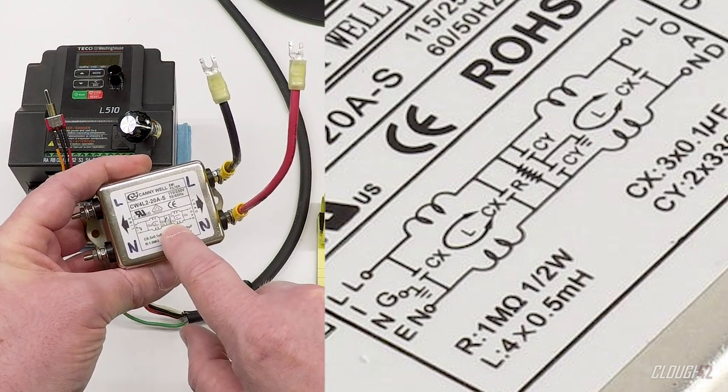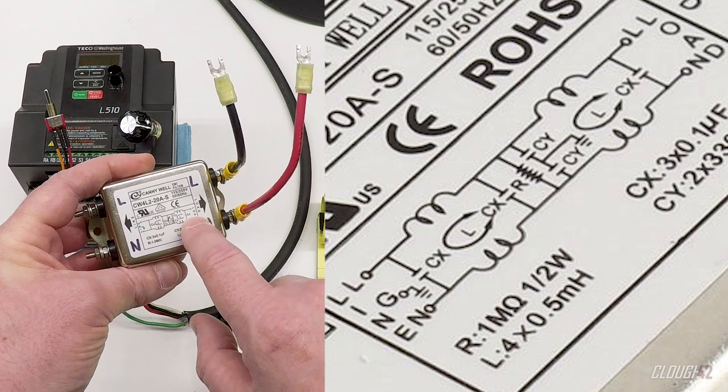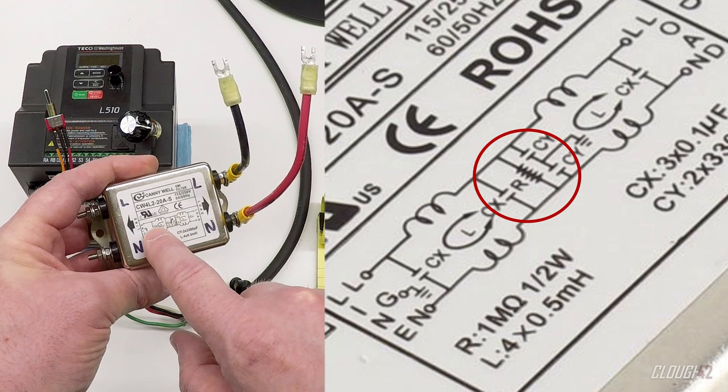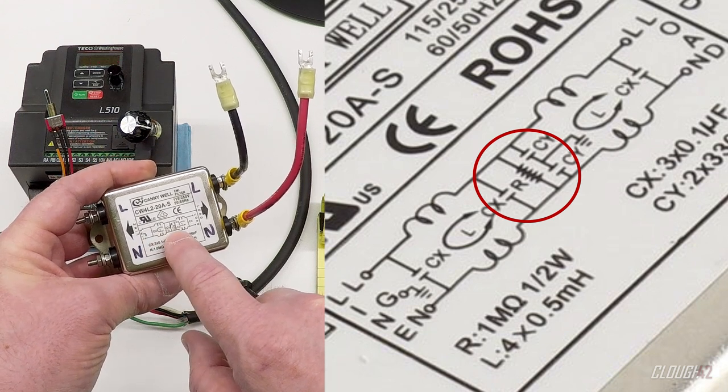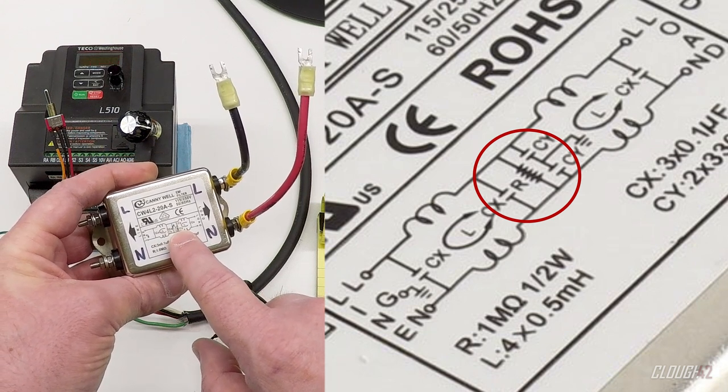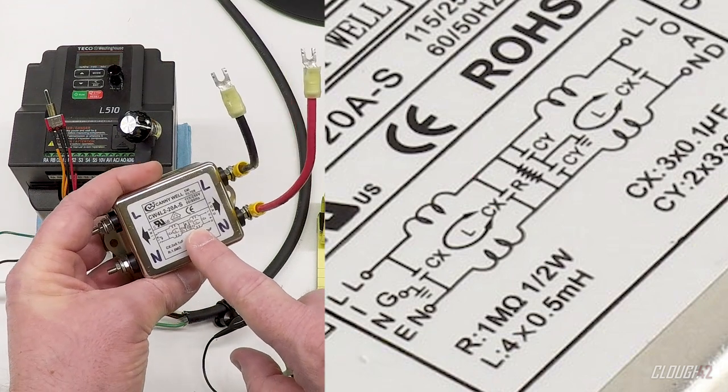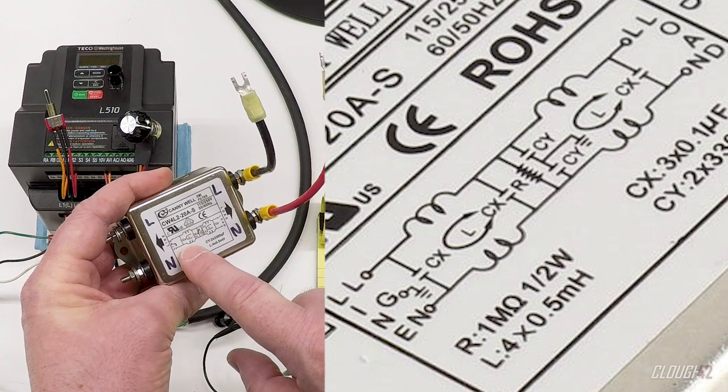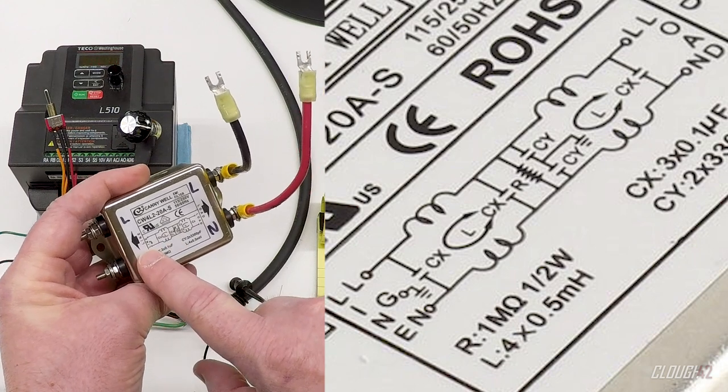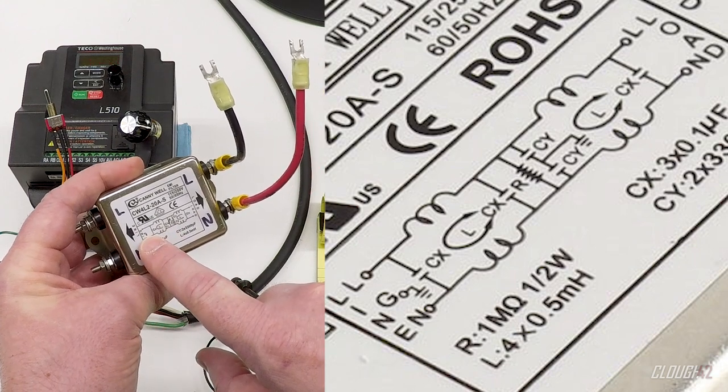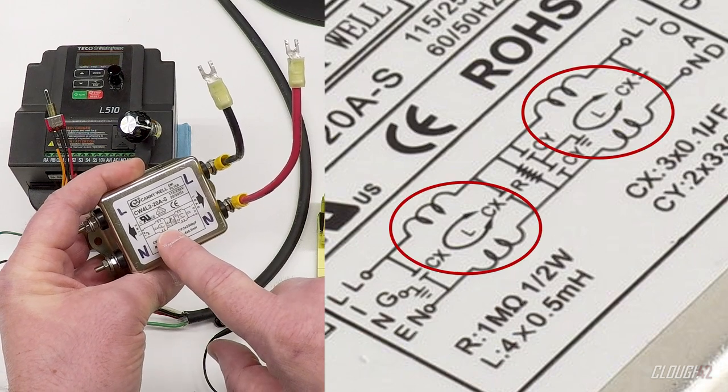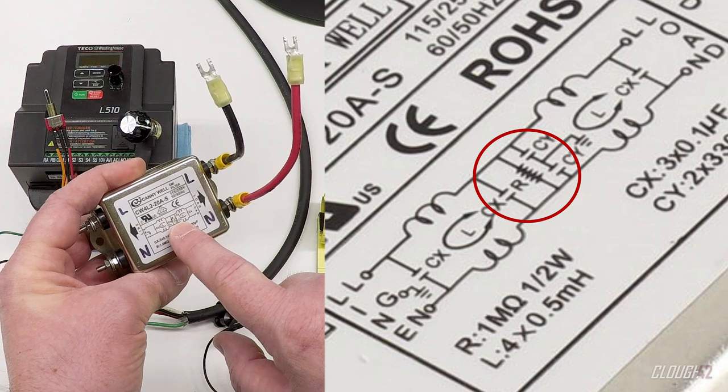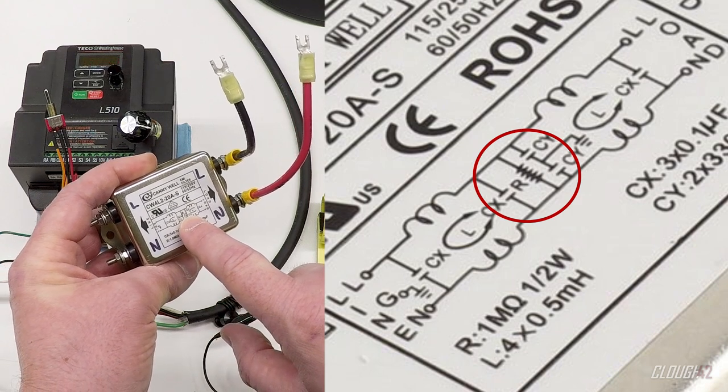So what's going on is we want to pass the 60 hertz power through this essentially unimpeded, but the higher frequency noise content we'd like to block. And so the way this works is it runs through these two series inductors. And the inductors look like a higher impedance, like a higher resistance, which weakens the strength, weakens the current of that noise energy that's going through. And then there are capacitors both between the line and the neutral and between the line and neutral to ground. And a capacitor looks like a low impedance to high frequencies.